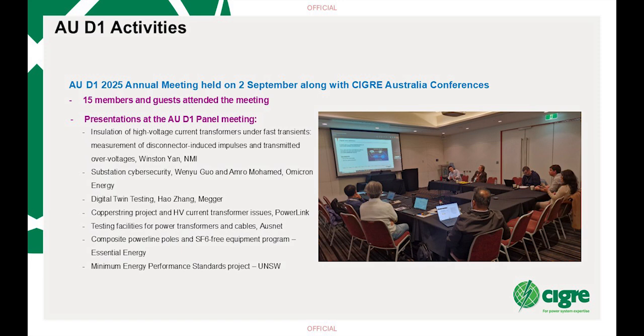We did some tests on faster transient measurement in the substation caused by the operation of disconnectors, in collaboration with Electranet. They found some of the CTs were damaged by the activity of disconnector opening and closing, which creates a pulse train of high voltage transients.